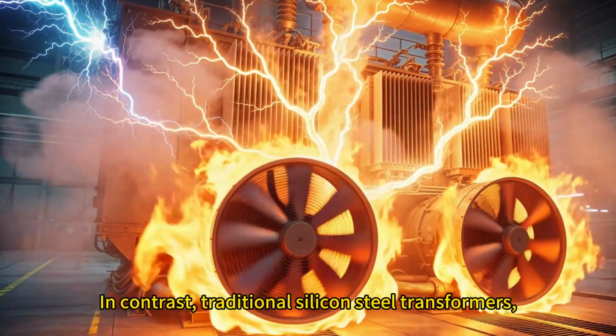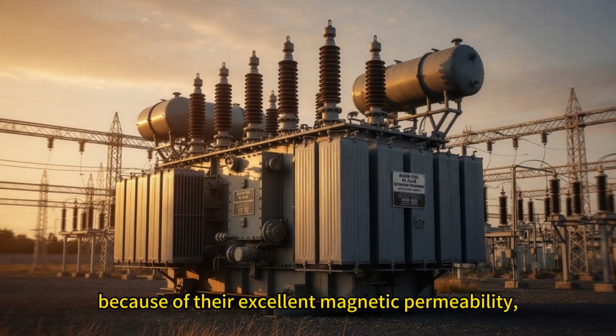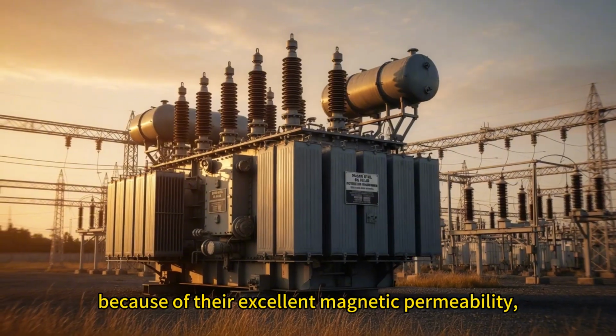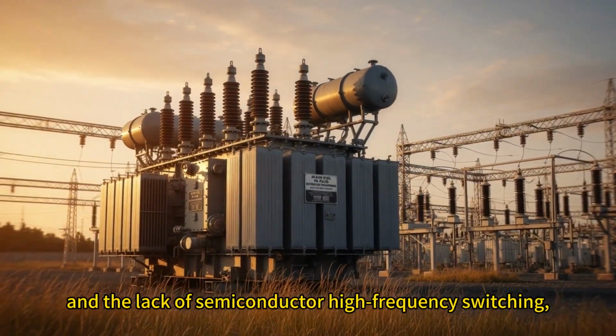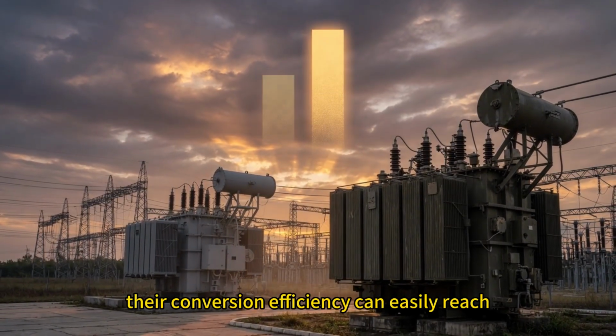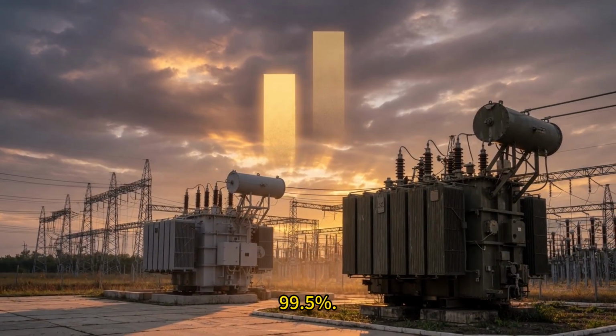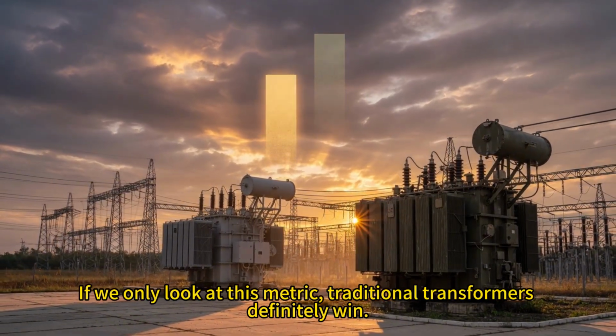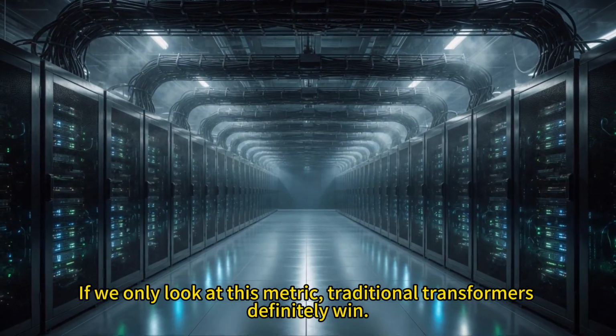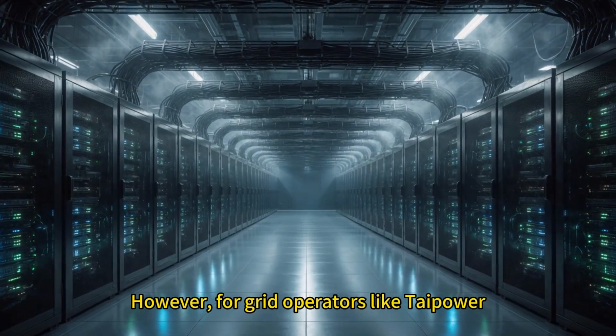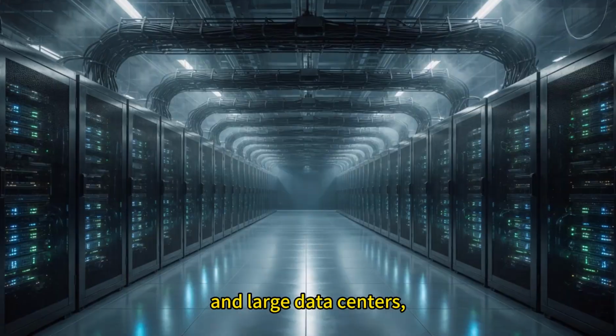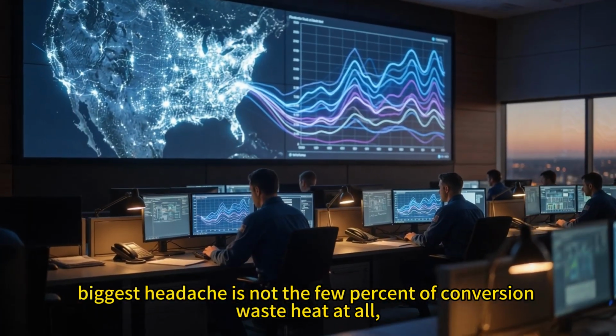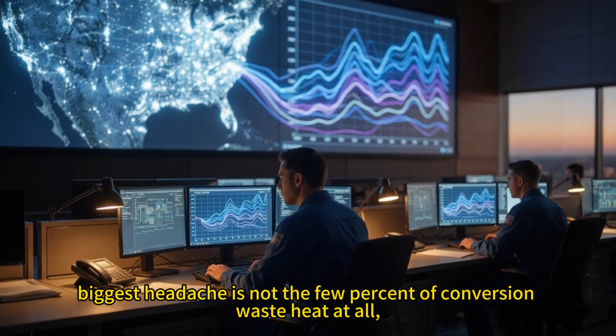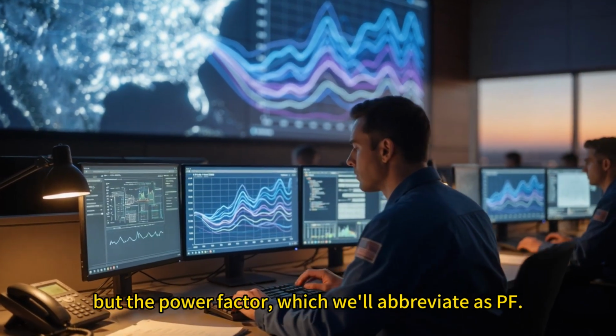In contrast, traditional silicon steel transformers, because of their excellent magnetic permeability and the lack of semiconductor high-frequency switching, have a conversion efficiency that can easily reach 99.5%. If we only look at this metric, traditional transformers definitely win. However, for grid operators like Taipower and large data centers, their biggest headache is not the few percent of conversion waste heat at all, but the power factor, which we'll abbreviate as PF.